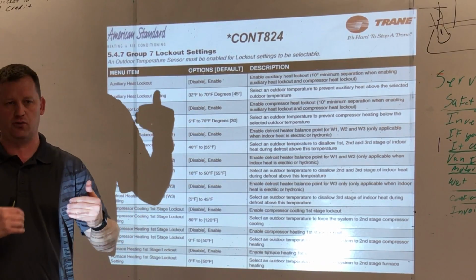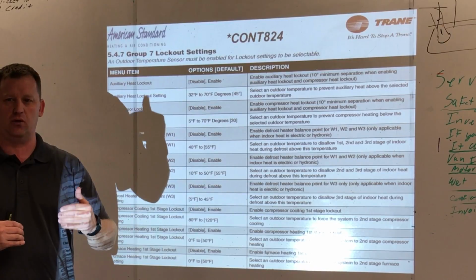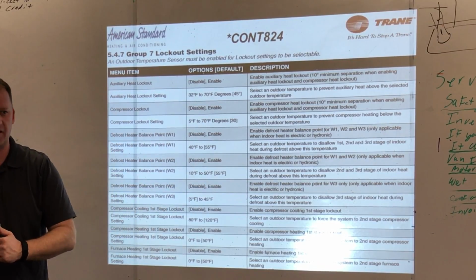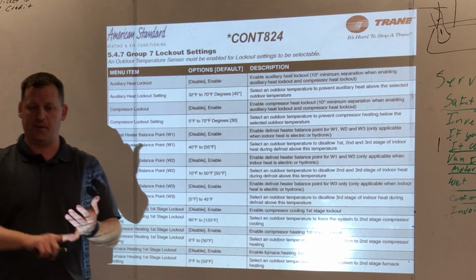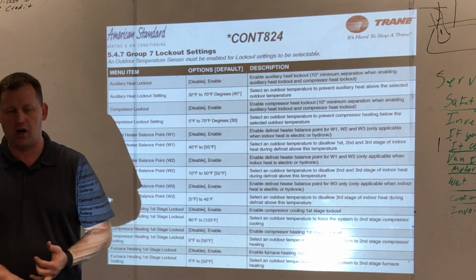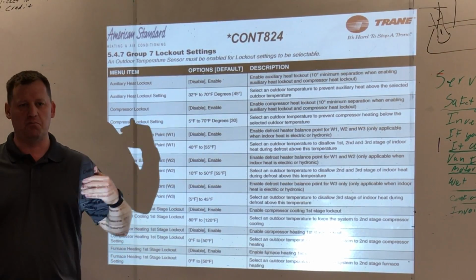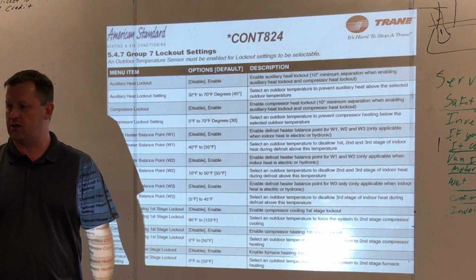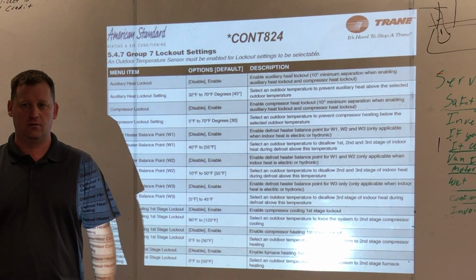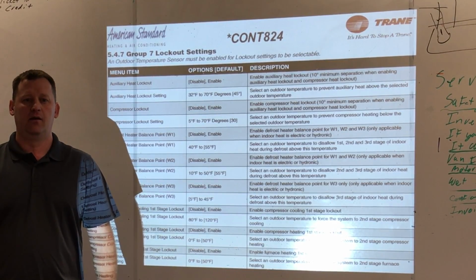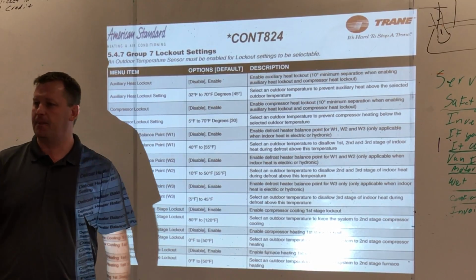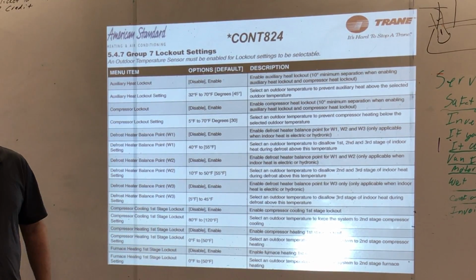We're going to kick on auxiliary heat at this outdoor temperature, and then we'll allow W2 to kick on at this outdoor temp. Because you're talking about thermal balance points, you're talking about economic balance points, and mixing the two. How many of you are going to sit down and do that math? No. You're going to have a lot of time on your hands to do that. And what's an engineer going to do? Let's figure it out. Sorry, this stat's not capable, but I can upsell you one that is.